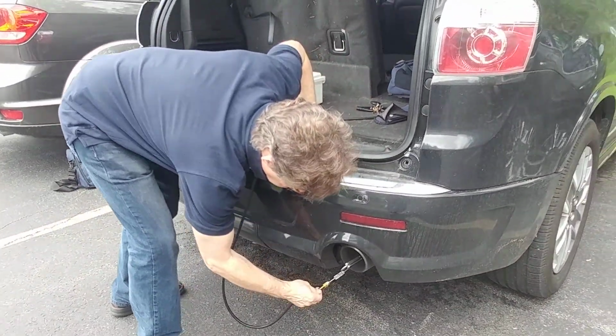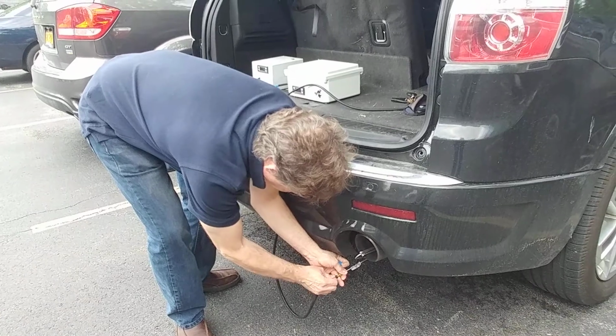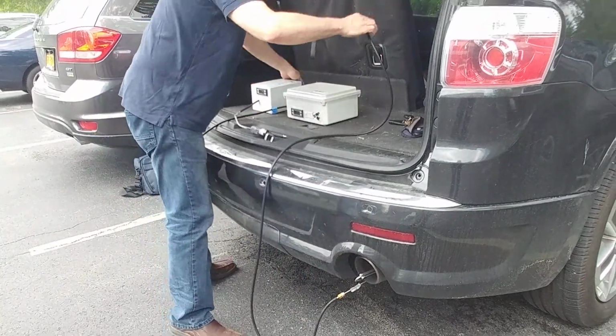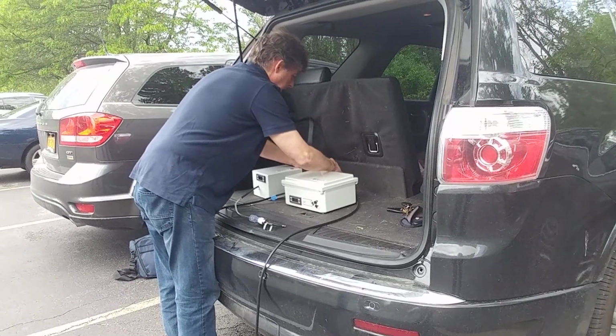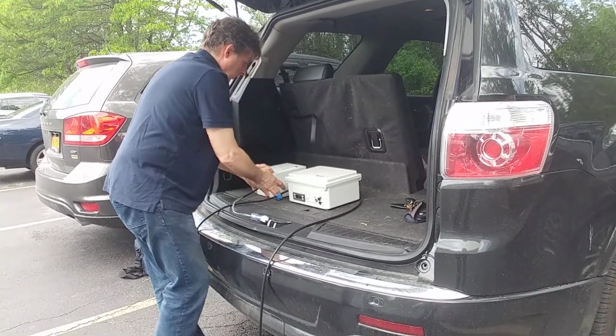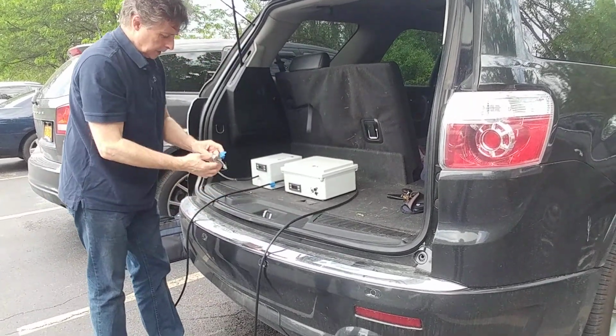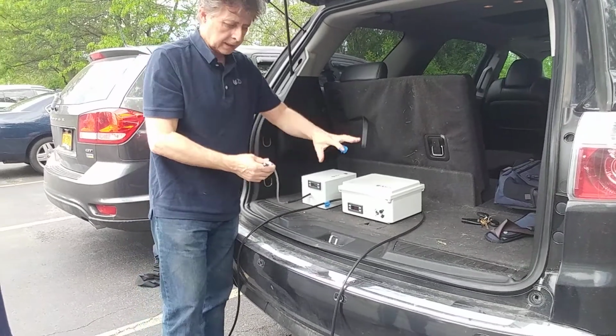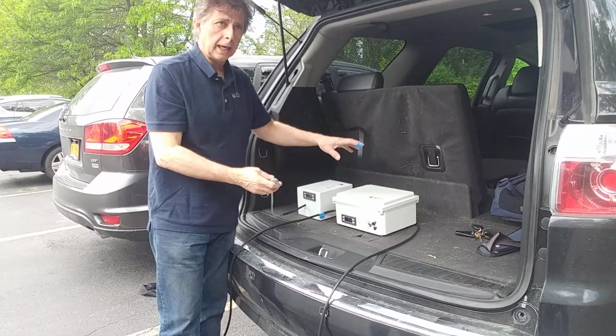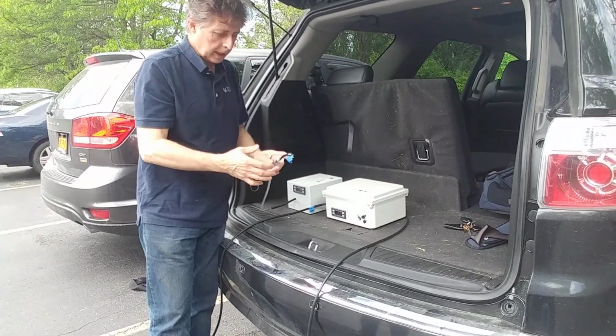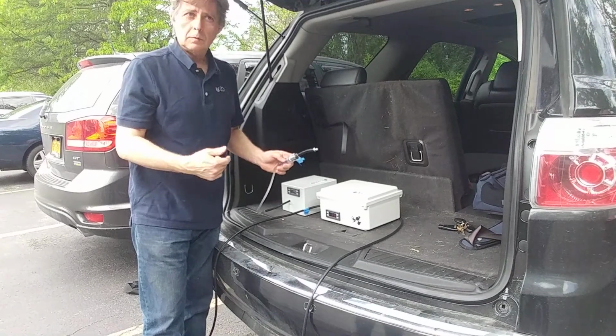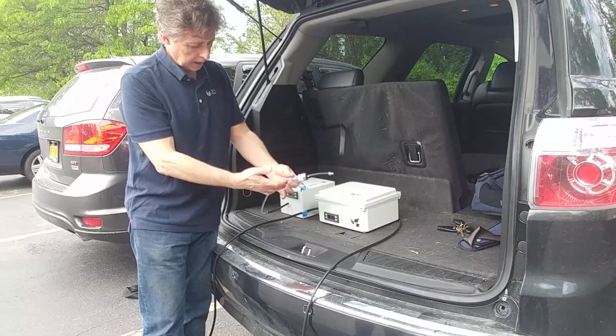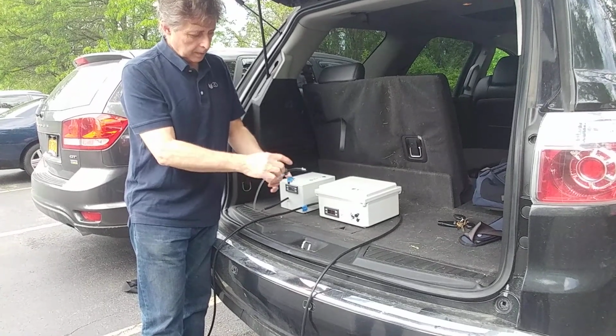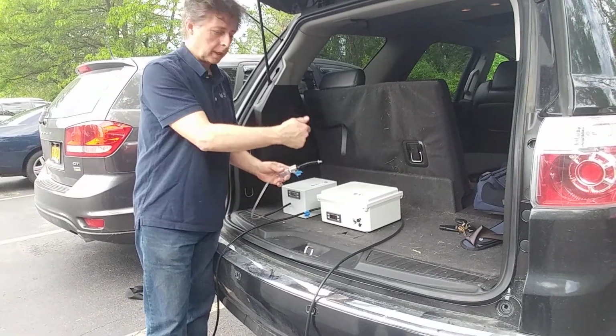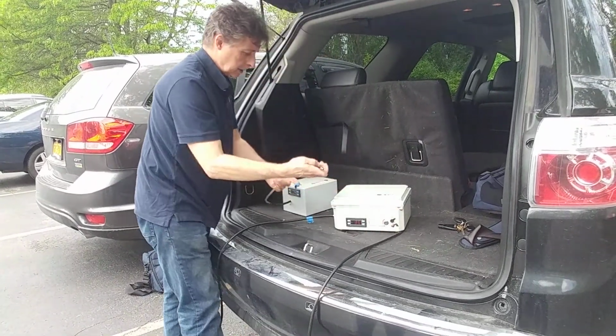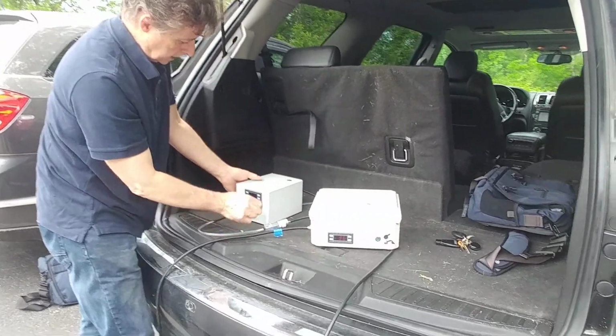That connects onto here, and that connects to the sample conditioner condensation unit. And so what we have is an extra trap to trap any possible water that could be in the line. Sure. This does a good job, but you might have some conditions that could give water. We have a visual inspection to see any water, but we definitely don't want direct water, condensed water, going into the unit. So this connects on the input side of the device.